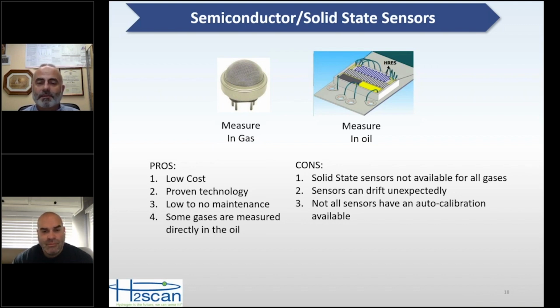But there are also solid state sensors that measure directly in the oil. And so this has a number of benefits. It's a simpler design. These sensors, when you measure directly in the oil, tend to last very long, with very good reliability, and there's no maintenance to them. So the pros are, where there is a solid state sensor available, they are generally lower cost. It's a very proven technology, with low to no maintenance, and sometimes they can measure directly in the oil depending on the design. The cons are that there are not solid state sensors available for all the gases. So it would be nice if you could have an 8 or 10 gas monitor with all solid state sensors, but so far that doesn't exist today.